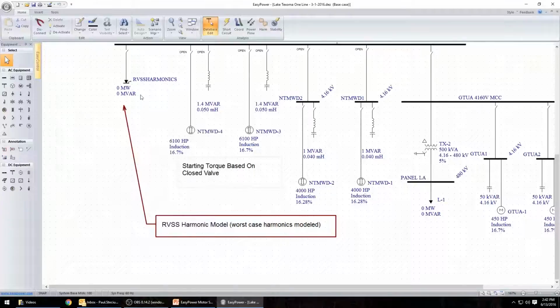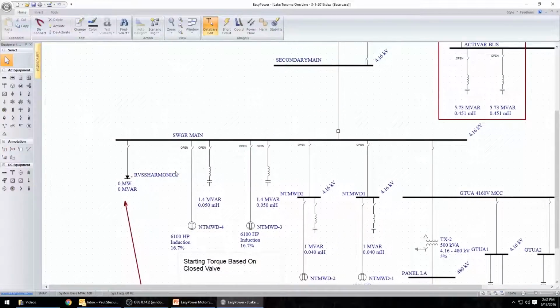So it's just like any other harmonic analysis. We account for the soft start harmonics here and look at how they respond to these capacitors here. So it's important that we make sure that there's no resonant conditions during the starting period that can result in fuse operation in these capacitors as well as those capacitors there.